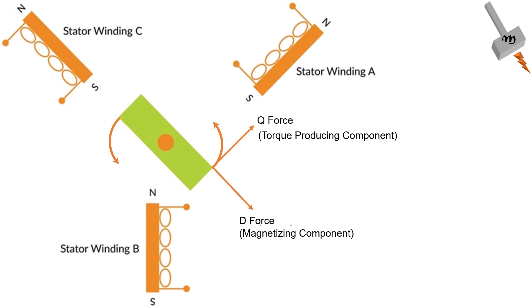Unlike scalar control, which operates based on a fixed voltage-to-frequency ratio, vector control dynamically adjusts the motor's current to ensure that the torque-producing component is kept orthogonal to the rotor flux. This results in higher efficiency, especially at low speeds or when torque is required. Vector control can be implemented in both open-loop and closed-loop configurations.